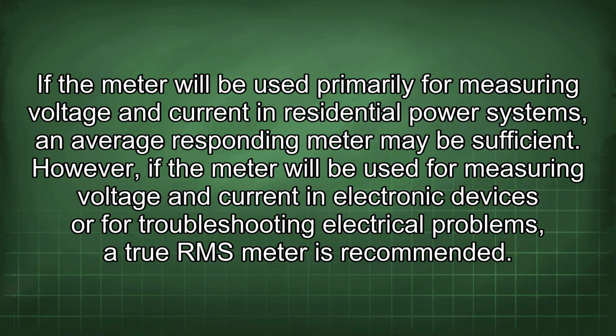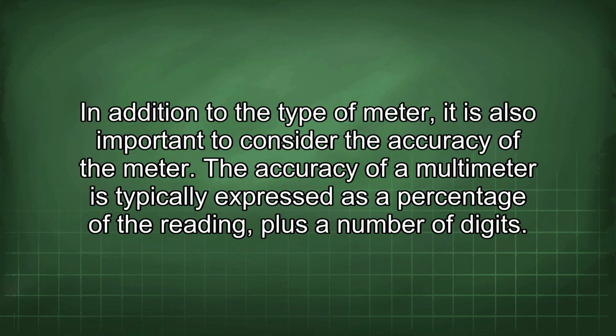However, if the meter will be used for measuring voltage and current in electronic devices or for troubleshooting electrical problems, a true RMS meter is recommended. In addition to the type of meter, it is also important to consider the accuracy of the meter. The accuracy of a multimeter is typically expressed as a percentage of the reading, plus a number of digits.